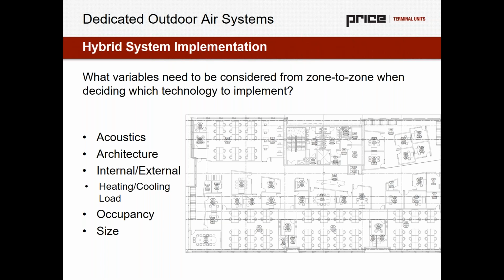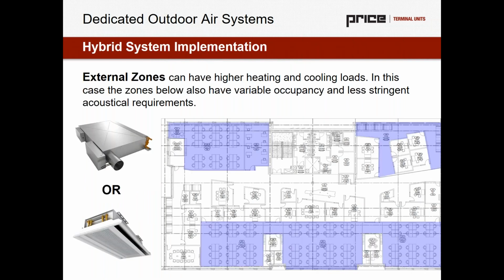We have to consider zone loads. Are we in an internal or an external zone? What's the heating and cooling load? What's our occupancy, and is it variable? And then generally, how big is the zone as well? So in the chat here, I'd be interested to see your thoughts. We'll start with external zones here, because external zones can have higher heating and cooling loads. In this case, the zones below also would have variable occupancy and less stringent acoustical requirements, as they're open office spaces. So in the chat, put FP for fan powered or put CB for chilled beam. What do you think would be utilized in this zone? Once again, FP for fan powered or CB for a chilled beam.